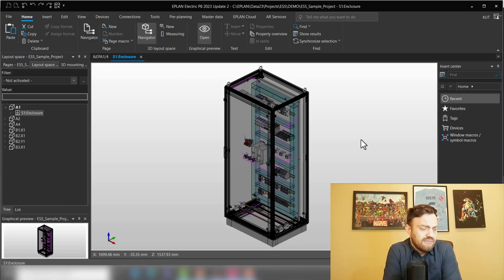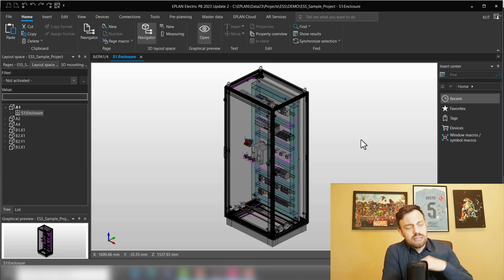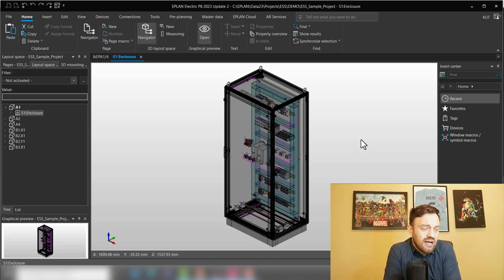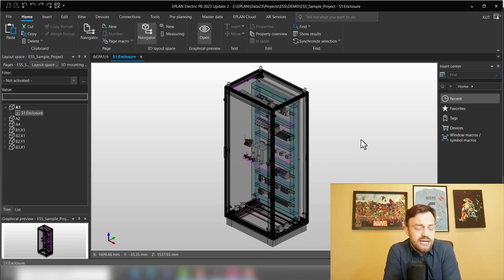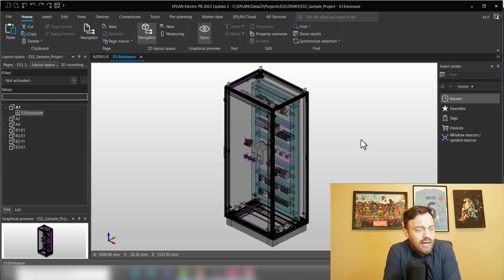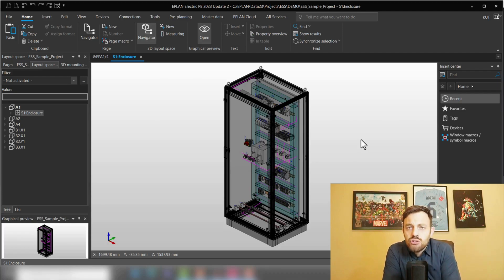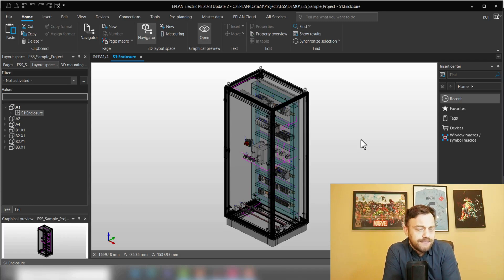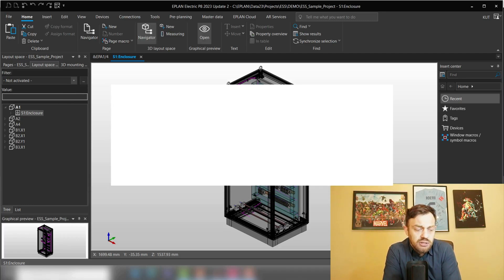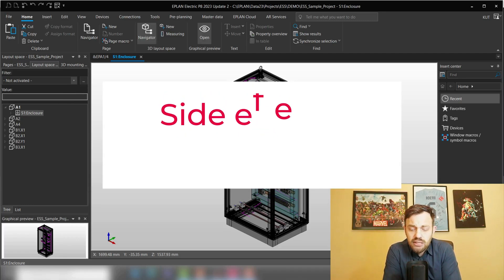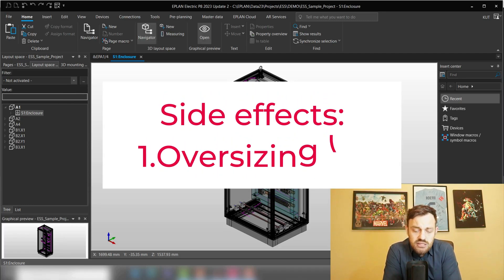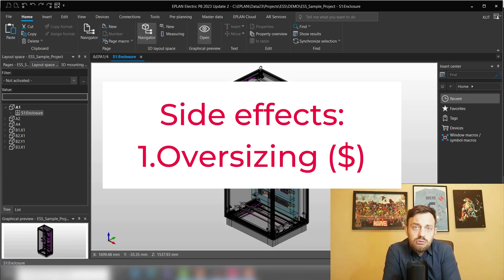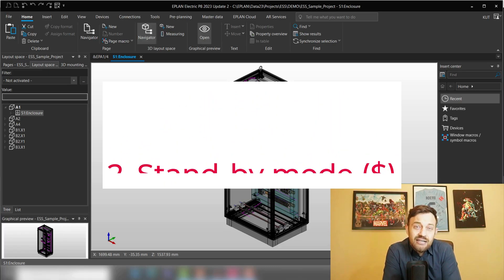Typically, customers would have in Excel, summarize the components, have an approximate power dissipation value for the enclosure, add a safety margin of 15 to 20 percent, and purchase the next bigger cooling component. What this does typically is that we are oversizing a cooling component.